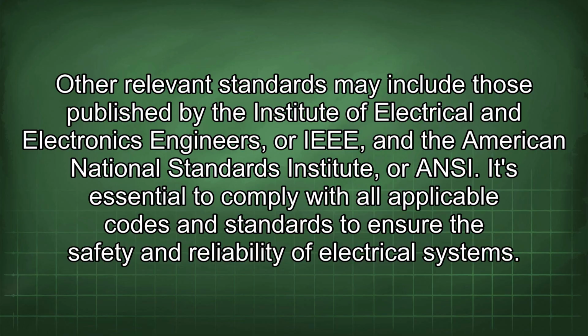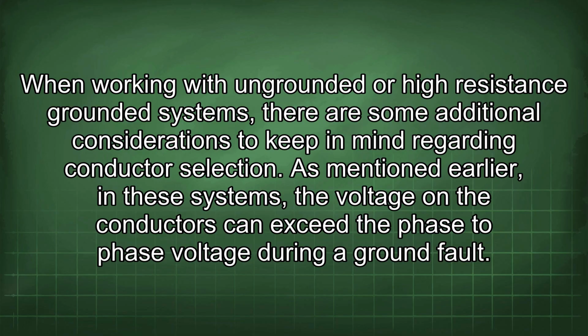It's essential to comply with all applicable codes and standards to ensure the safety and reliability of electrical systems. When working with ungrounded or high-resistance grounded systems, there are some additional considerations to keep in mind regarding conductor selection. As mentioned earlier, in these systems, the voltage in the conductors can exceed the phase-to-phase voltage during a ground fault. Therefore, it's crucial to select conductors that are rated for the maximum voltage that may occur under fault conditions.